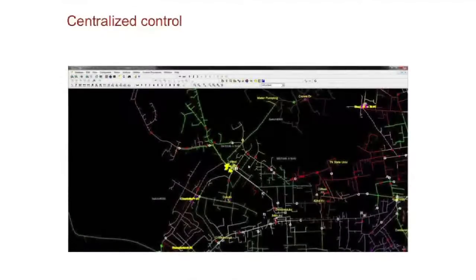So this one says, my 50P-1 picked up. Who's interested in getting that message? This message goes to the one upstream, which says, I'm interested in that because I care about the coordination, so I'm going to subscribe to that message. So via GOOSE messages and peer-to-peer communication, it blocks all instantaneous elements on this upstream recloser. In this case, you could also do transfer trips between this device and this device. Once this one detects a fault, it can initiate the trip signal to the interconnection point. And when this one opens up, it sends a status message to this RER620 saying, allow me to reclose.